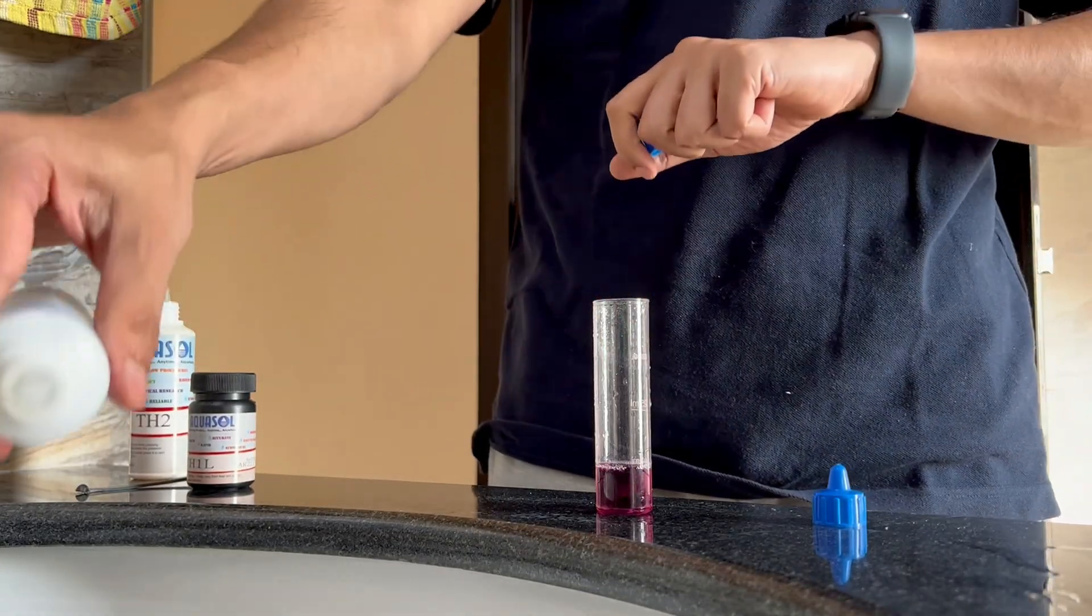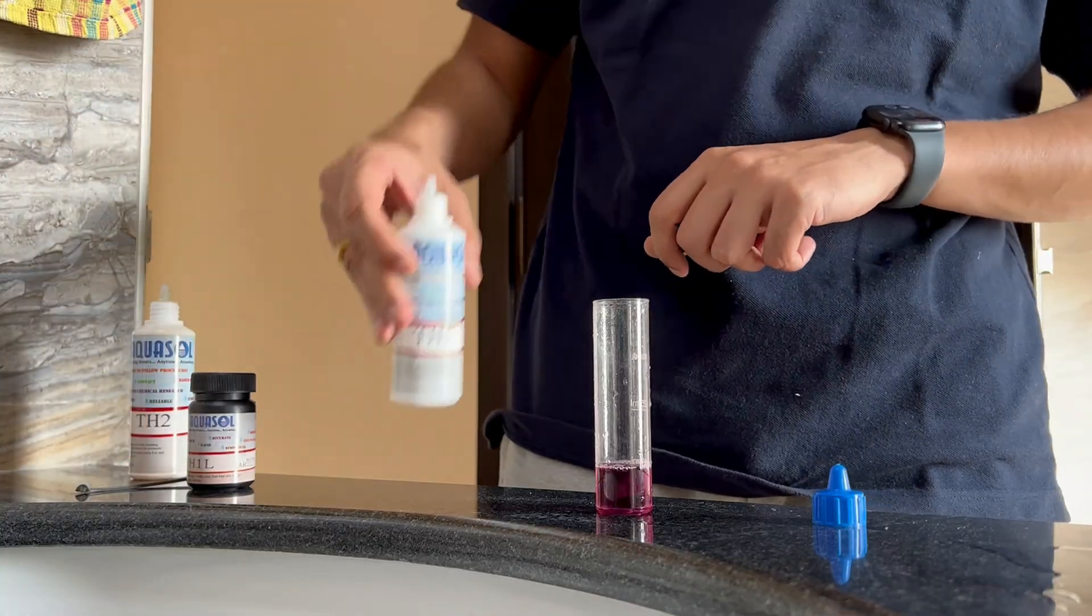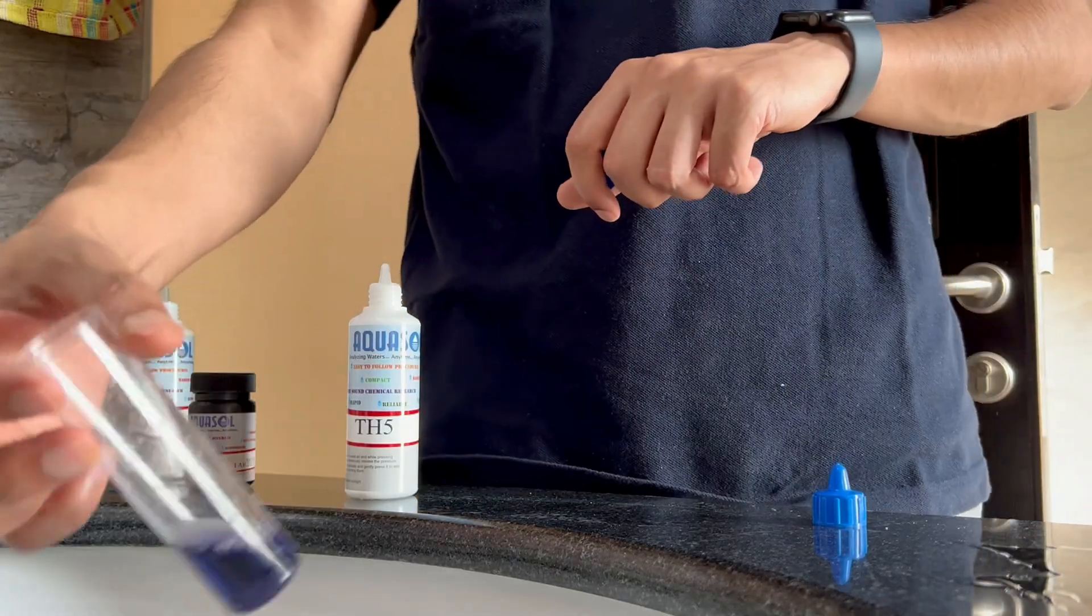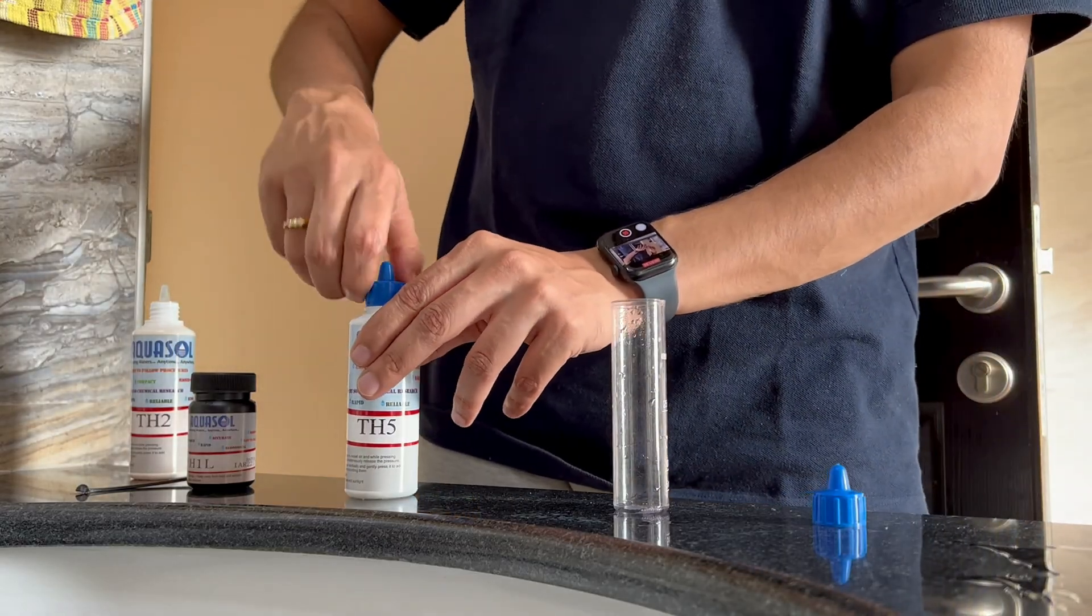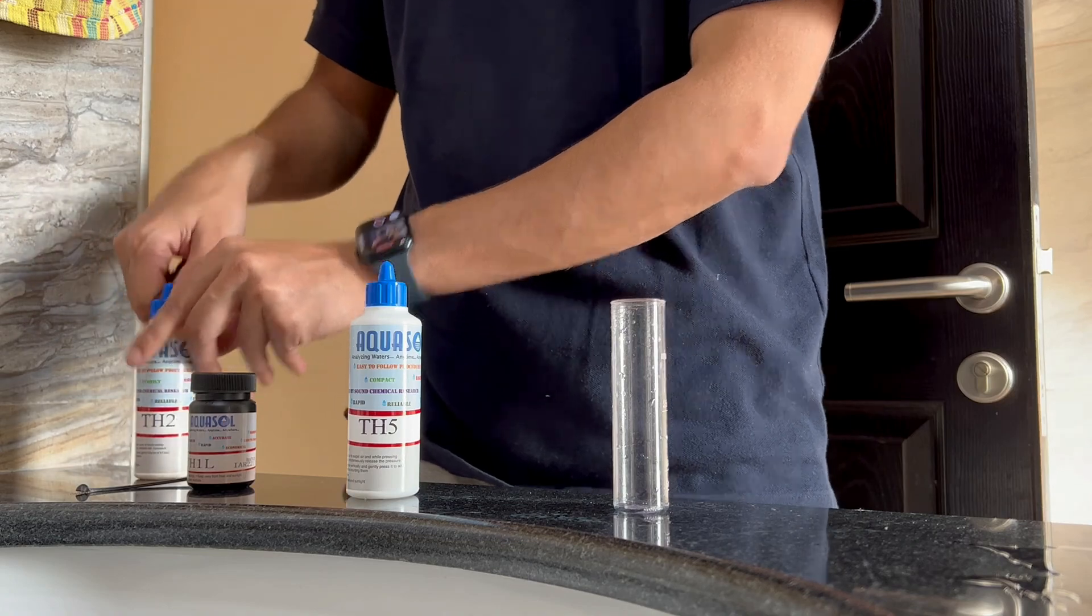TH5, one drop is equal to 25 ppm of hardness so I'll put one drop, mix it well, and there you see the water turns to blue. So the hardness is 25 or less at the moment, reduction from 750 and that's a big reduction. The water is very good and safe and soft to use.